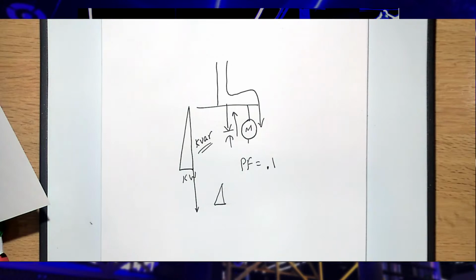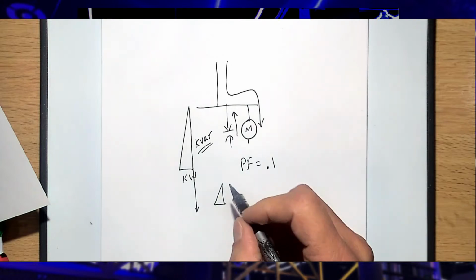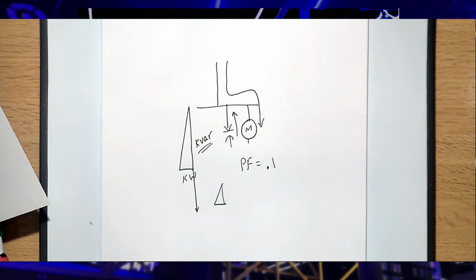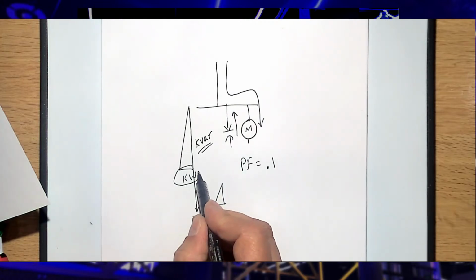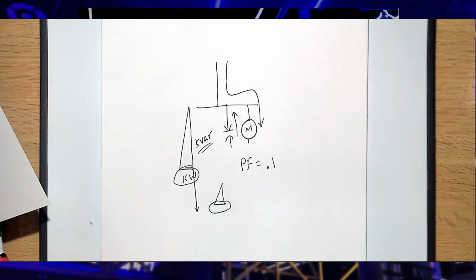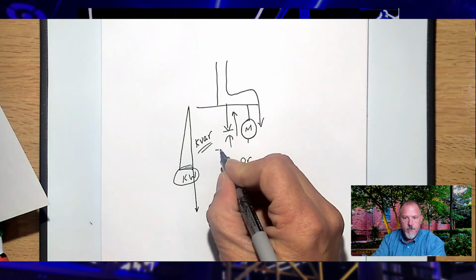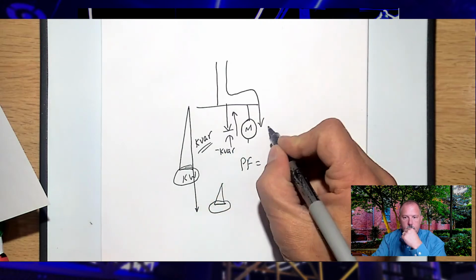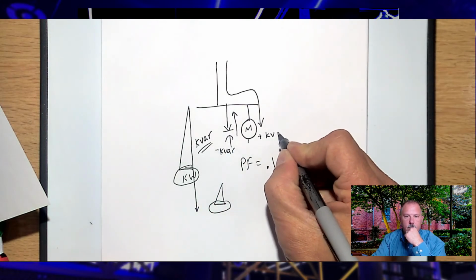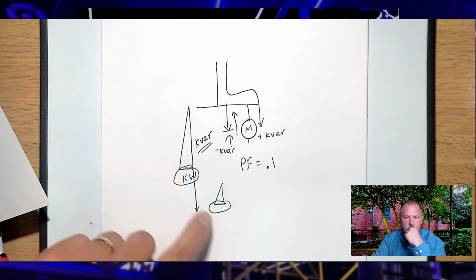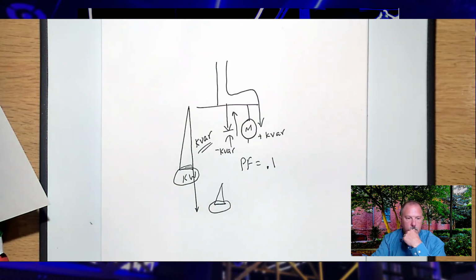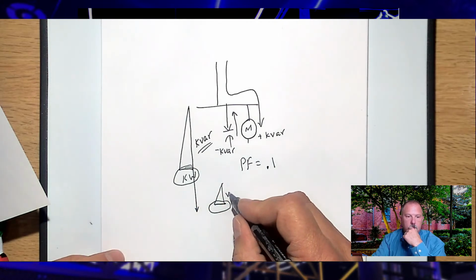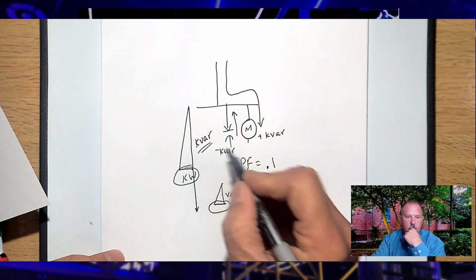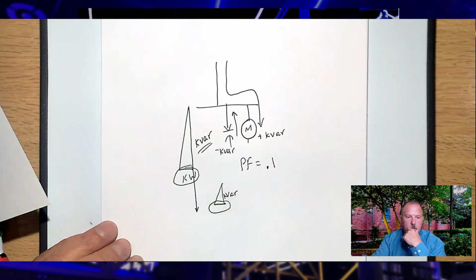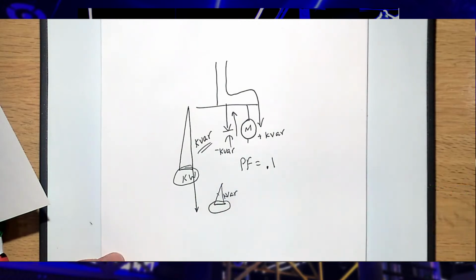So what you're doing then is your VARs are subtracting from the VARs that the motor's putting in. This is minus kVAR, and this is plus kVAR. And so what happens is your kilowatts don't change, because you're still trying to overcome the friction of the motor. But what happens is your VARs change. And what also changes is your kVA, the hypotenuse of the triangle.